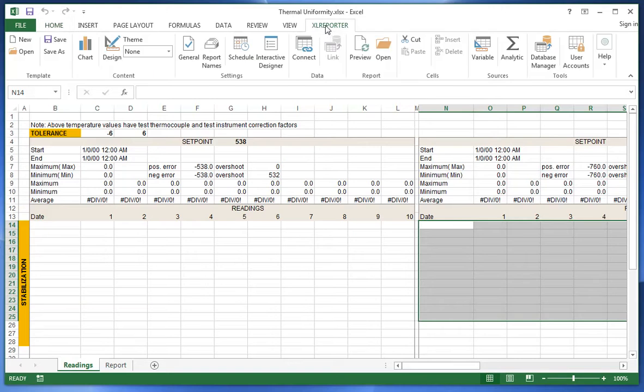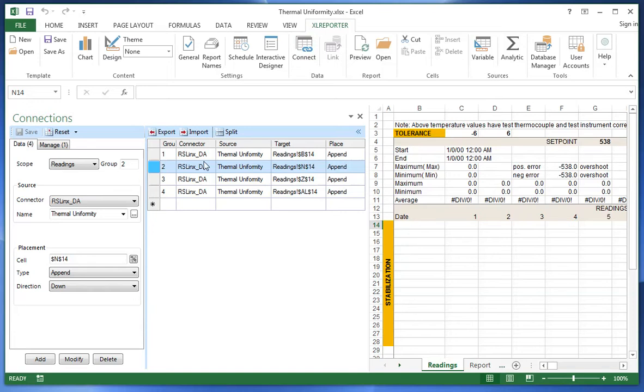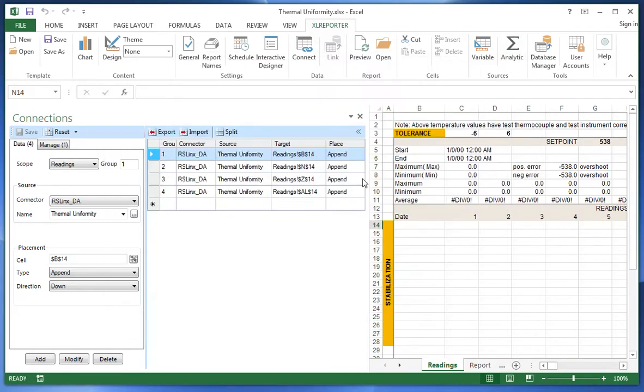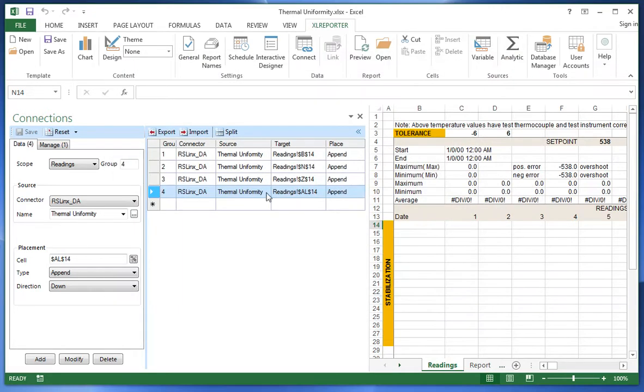The readings are put into this report through connections to the RSLinx. What I have here are 10 thermocouple readings and they are going to be placed at B14 and they're going to be appended down if the current row is occupied with data. Likewise, this is also the 10 thermocouple readings with the timestamp on the first column and those values are going to be put in AL14 again going down.